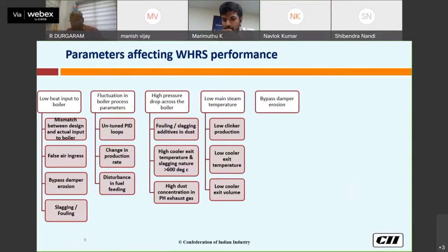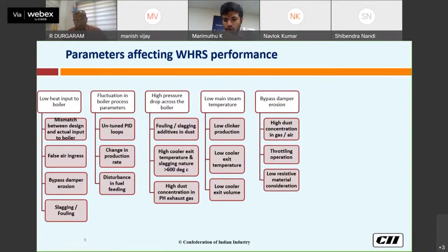Then another one is bypass damper erosion. The bypass damper erosion might be due to the high dust concentration in the gas or air, or it is due to the throttling operation. If you are operating the damper with slight bypassing, maybe 10% or 20%, then in that opening the velocity will be more, because the vacuum at the bypass damper will be more than at the WHRS system. So it will suck more air from the damper only, which automatically increases the velocity and causes the erosion. And low resistive material consideration: during the design stage, if the damper is not designed with a high wear resistant material to take care of the dust, it will cause the erosion issue.